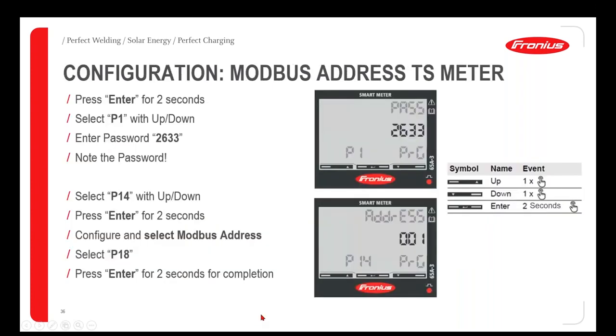We'll also then just need to change the Modbus address for each device. So we need them all to have their unique address so that we can identify each meter individually. And this is done through the meter display. So the buttons on the screen of the meter, they're touch sensitive, hence the name TS. And one press incrementally increases and decreases the numbers on screen. And the long press, enter, is the enter button to accept a setting.